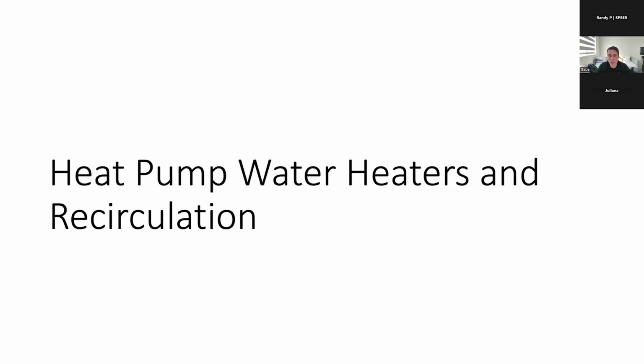Last but not least, I want to address heat pump water heaters. I don't know how prevalent heat pump water heaters are yet in the Texas market, but I can tell you they've hit the California market like a tsunami. It was literally like a switch being flipped. When I moved to California, it was all tank water heaters in new construction. Then the energy code went into effect: it's got to be tankless, and then it's got to be condensing tankless. And now everything installed in California has to be electric heat pump water heaters. So the pendulum has swung right back to tank water heaters.